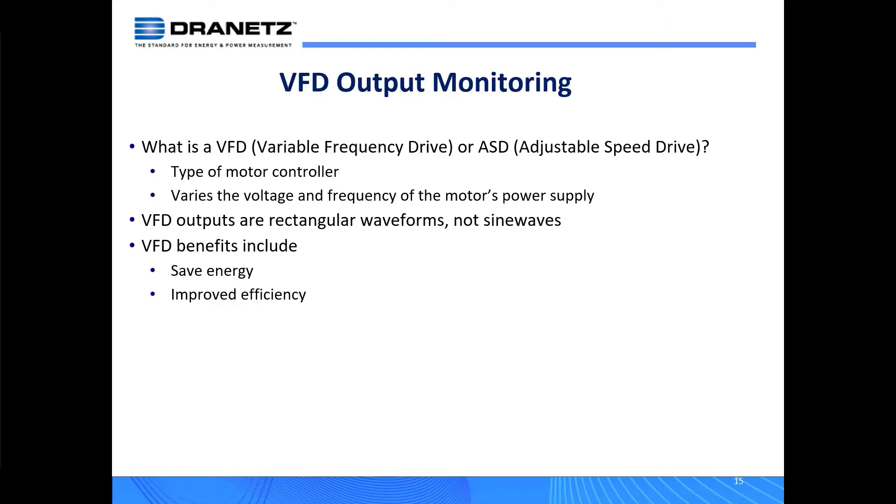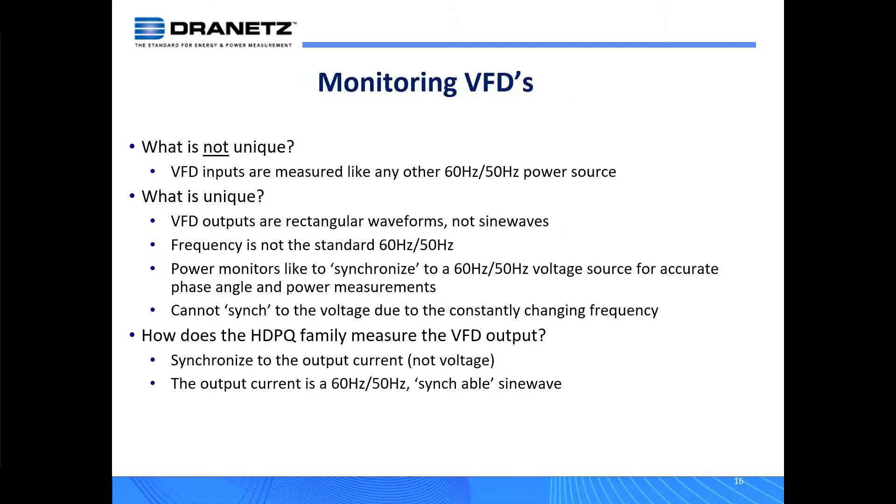One of the basic things is that VFD outputs are rectangular waveforms, not sine waves. And they're not 50 or 60 hertz - they vary in frequency, hence the name VFD. So that presents some challenges for a power monitor.